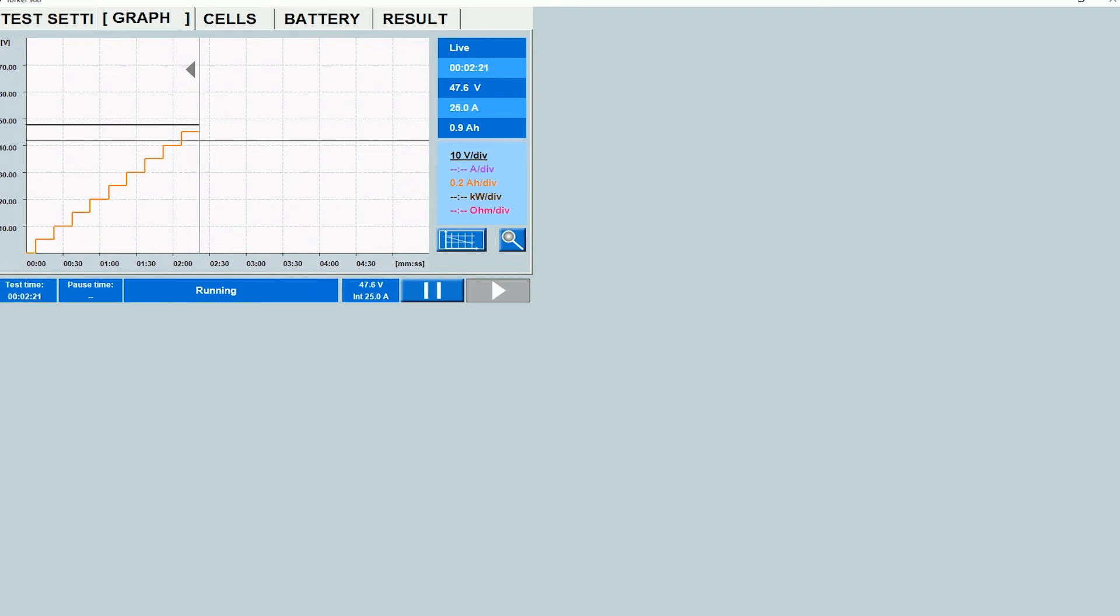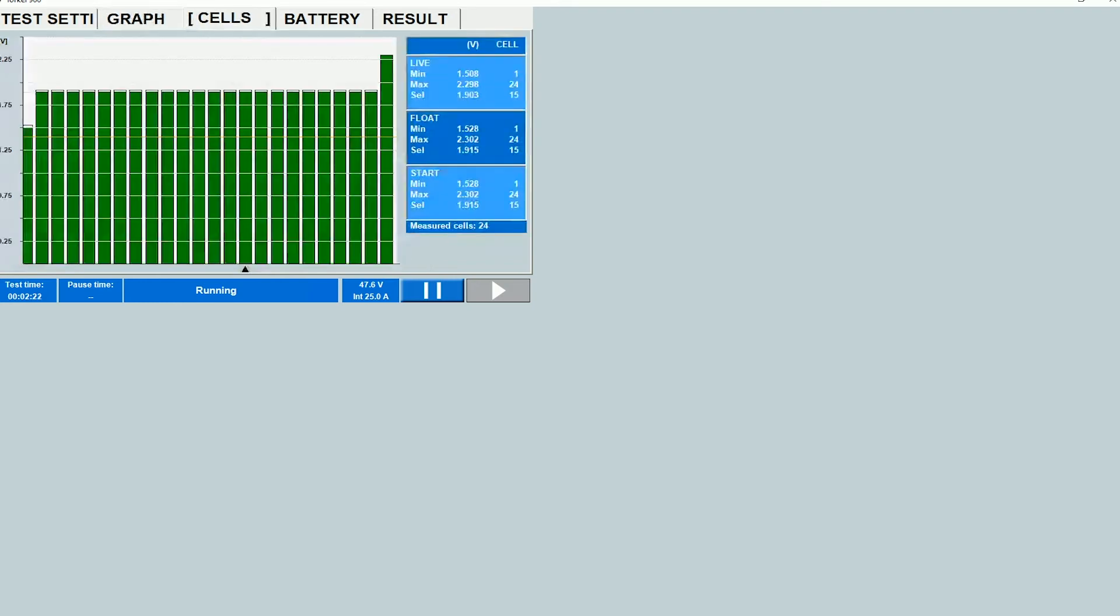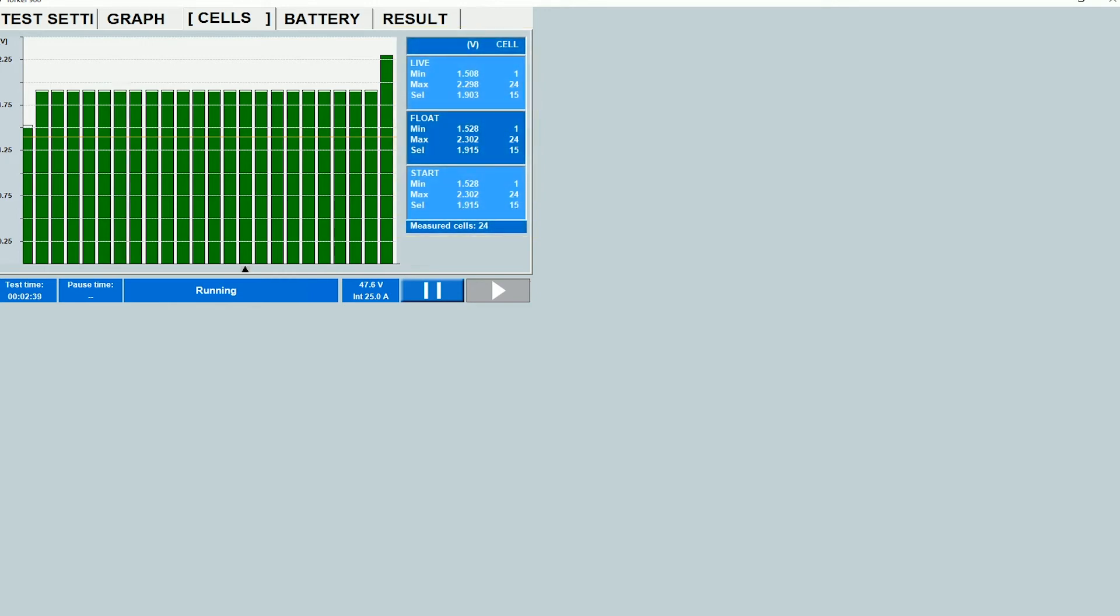Let's go over to the cells tab and see what information provides. Now here you see the starting values as well as the live values. On the right here it kind of gives you a summary of the values. What it gives you is three types of parameters, the live voltage values, the float voltage values and the start voltage values. So float values as I said earlier are the values which were measured when the charger was still on and the start values were measured at the moment the test was started. Live values are current values.